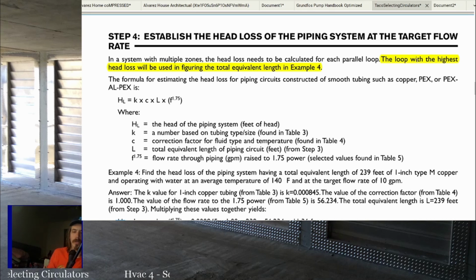When we learn about sizing duct, we're going to talk about the largest loss, the longest return line, and the longest supply line. Same thing with this. If you have multiple zones, your total equivalent length needs to be placed on the farthest zone. If the house is one big zone, then it doesn't matter. You calculate everything in the zone. If you have 4 zones, you'll have to find which zone has the most head loss, the longest equivalent length, and use that as your basis. You won't add all the zones together, because as long as the pump can handle the longest zone, it can handle the smaller ones. And that's the same for everything else.